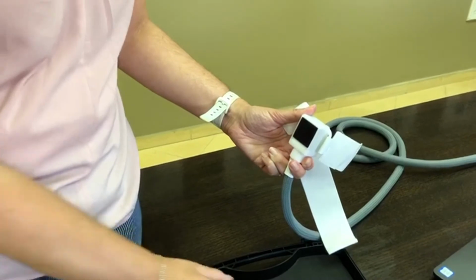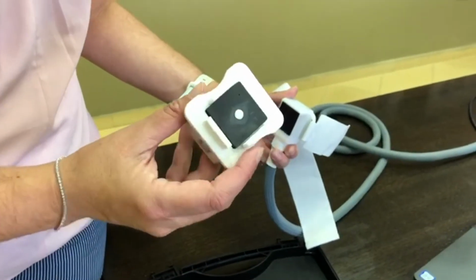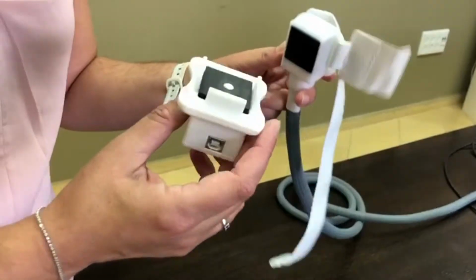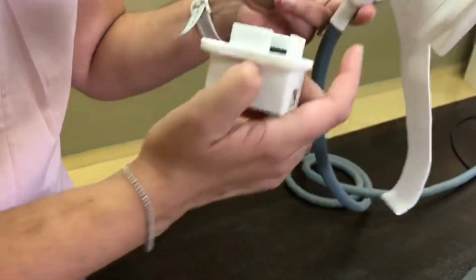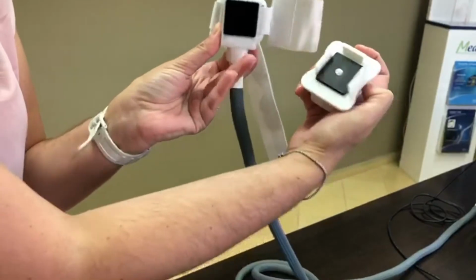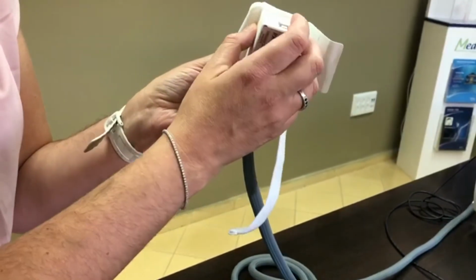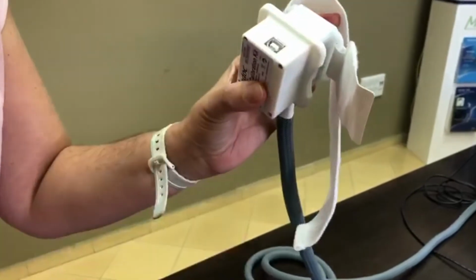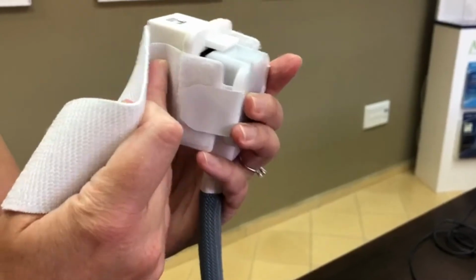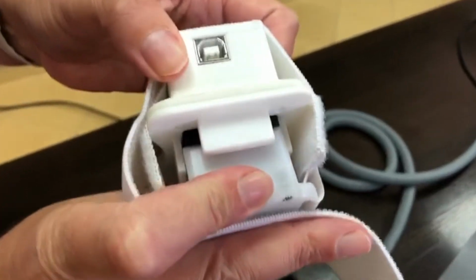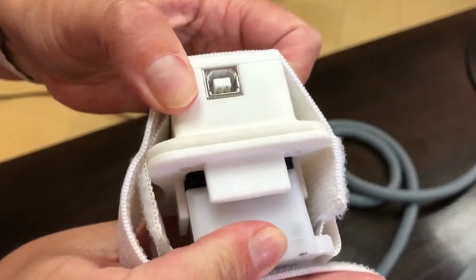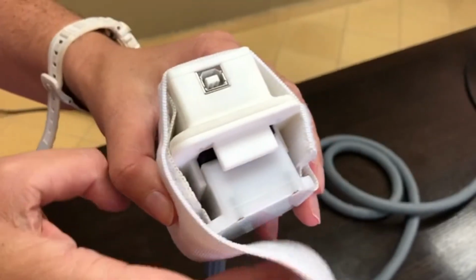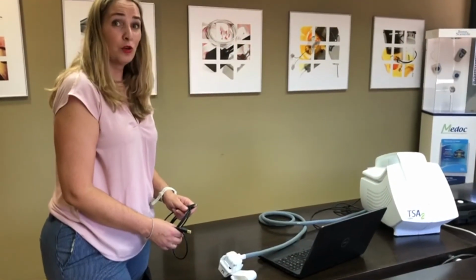So let's put it all together. We've got our sensor and jig. We've got the thermode. Now pay attention that the thermode cable needs to come over here on this side where the writing is, like this. Hold it all together tightly, and now close it up with the thermode straps so that it sits tightly and has good contact all over. And I'm pulling it, and I can't really pull it apart. So this is the way it should sit. You're almost done. Now we just have to connect this to the computer.